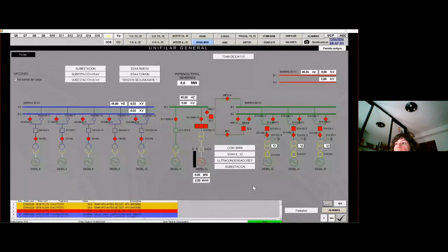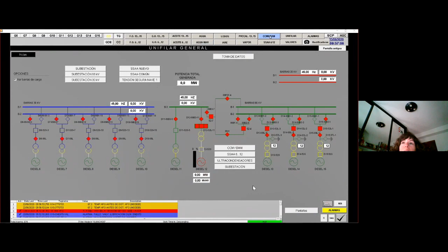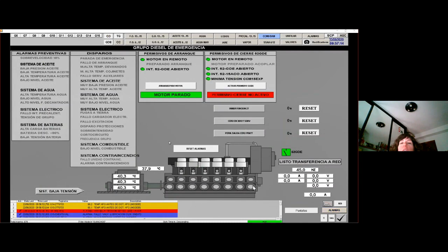Now, the diesel group should start up automatically, but as I mentioned before, we have blocked it. We put the diesel in manual local mode, so now the operator has to realize the diesel hasn't started.